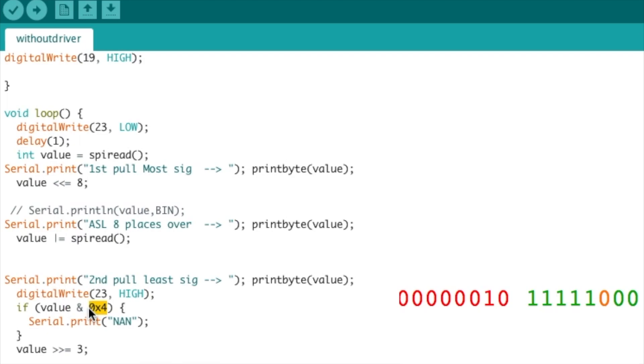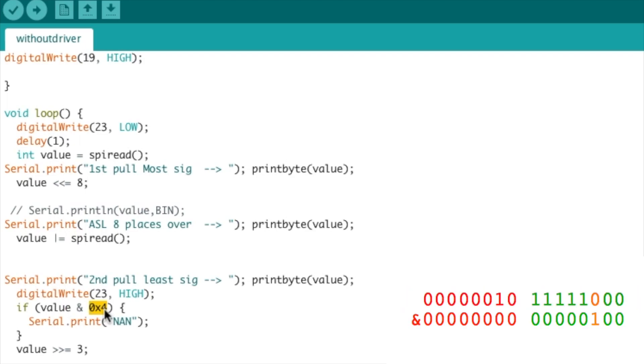It's a resistance value that it uses to read to make sure that the portion that actually senses the temperature is connected to the device. We can see that it's masked in hexadecimal 4, so it's a third bit over, and if the third bit over is high then it knows it's not connected.